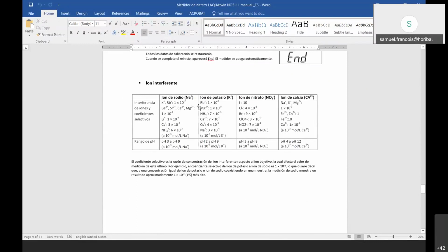Sorry, it's just easier for me in the Spanish version, but I will explain. So for example, for nitrate, we can see there's an interference of 10. So what does this mean? It means that every ppm of the concentration of iodide in the sample will be showing as 10 times more of nitrate. So let's say you measure a sample which has 10 ppm of nitrate and 10 ppm of iodide, this iodide is going to measure as 100 ppm of nitrate. So you're going to get a 110 ppm measurement.